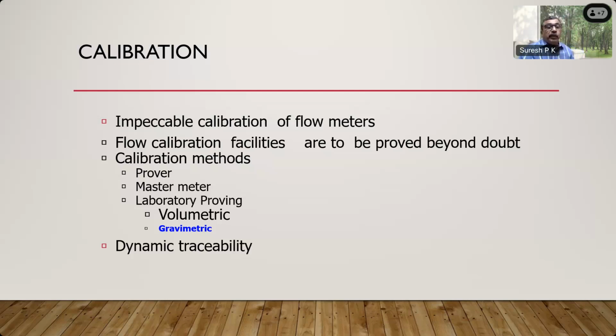In laboratory proving, the meter is taken to the laboratory, and what is passed through the meter is collected either in a volumetric tank or in a gravimetric tank. Gravimetric means the mass of the fluid is measured. This is then compared with the flow meter indication. For example, if the flow meter indicates 100 cubic meters and the actual volume is 99.5 cubic meters as per the volumetric tank, then the inaccuracy is 0.5%. For gravimetric, the same system is used.